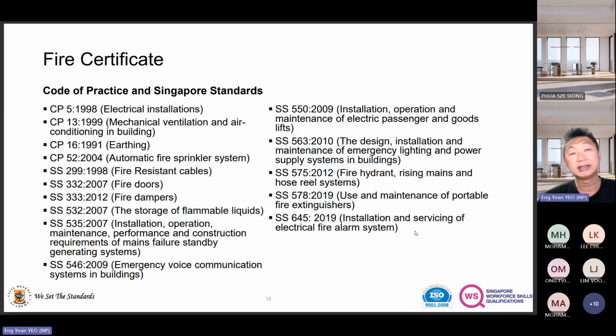Ideally, it would be good to have a detailed plan showing exactly where each heat detector and smoke detector is located, so testing can follow that schedule. That would be the ideal situation, if someone could do it really thoroughly, which would be very good. But in reality, on a day-to-day basis, because of high staff turnover or not getting the same QP, things may not be as comprehensive as they're supposed to be.